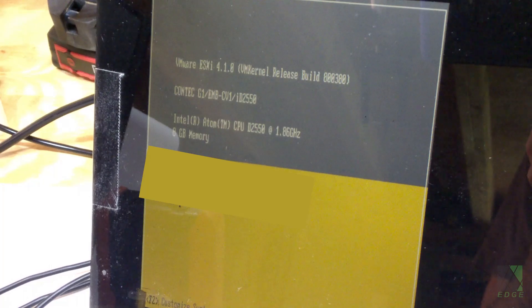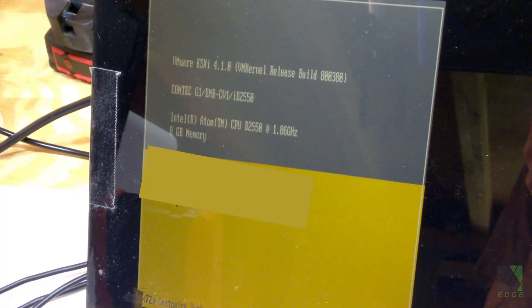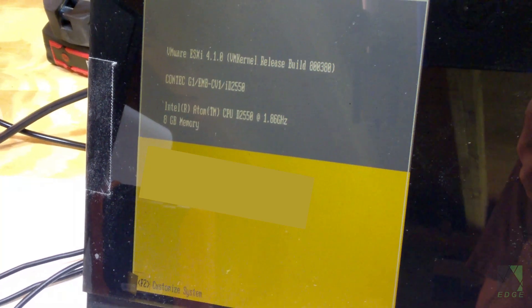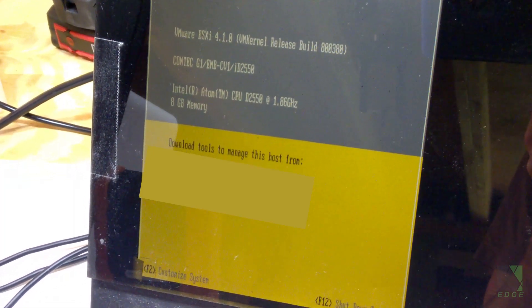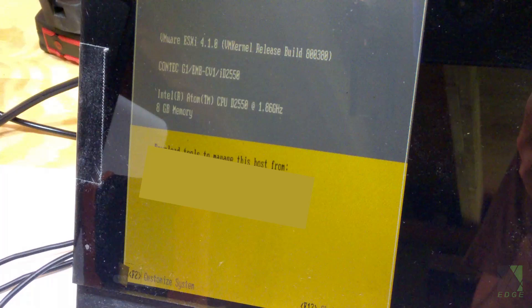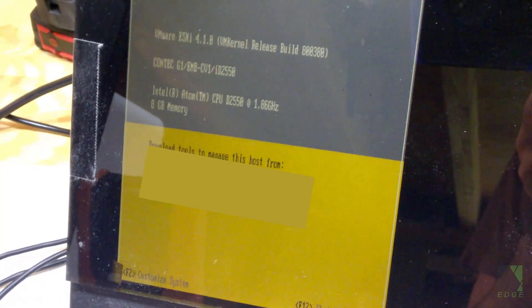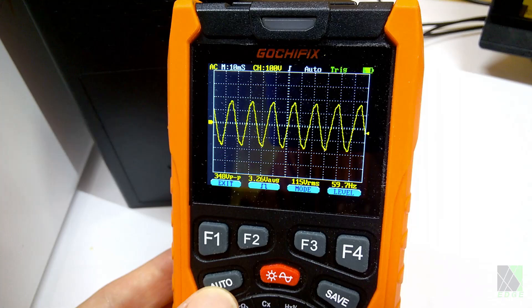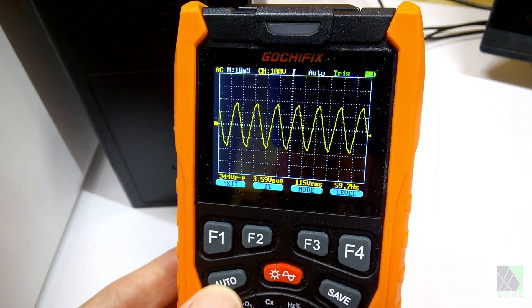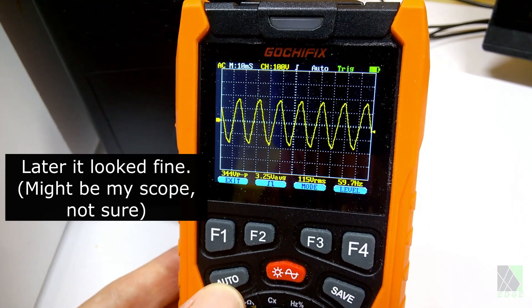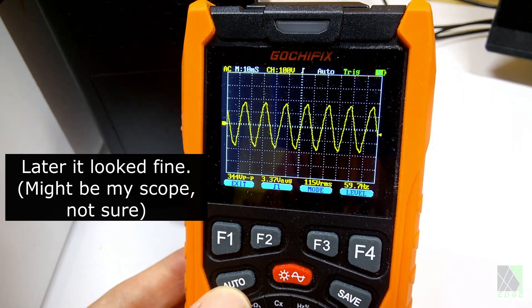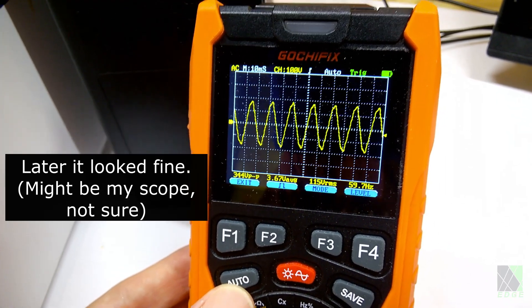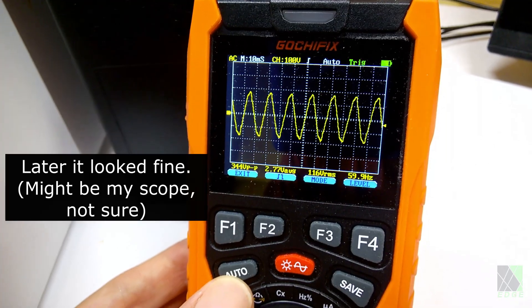And just to show that the system is running, there's the screen. It's really hard to see because it's a small monitor, but I just want to show that it is booted up and it is running. This is not a desktop computer. It's a really old server environment, but it's good enough for the test. There's what the output looks like on an oscilloscope. It is more or less a sinusoidal waveform, and it looks a little bit different at the peaks, as you can see. Now, I'm not terribly worried about that, but let's go ahead and do a test and just see how it performs.